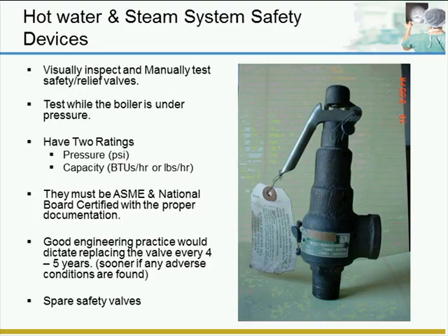Good engineering practices would dictate that every 4 to 5 years, high-pressure safety valves should be replaced. If any adverse conditions are noted, or during a test there's a condition that is noted, they should be replaced sooner. It's always good to have spare safety valves on site. If you do a test on a safety valve and it isn't properly reseated, it takes minimal time to replace the safety valve if you have a spare unit on site.